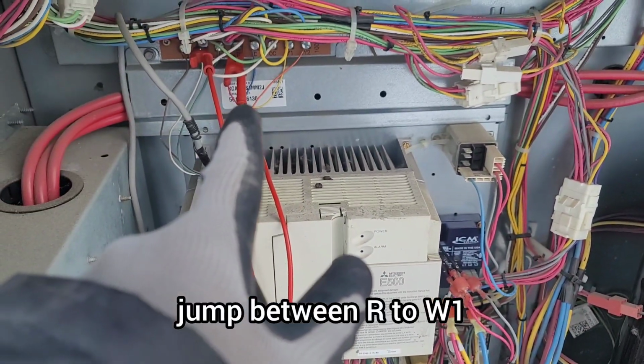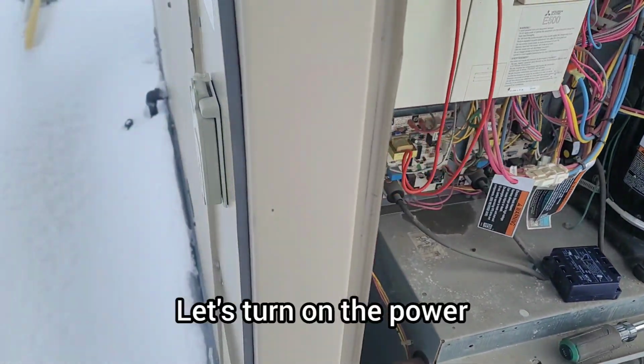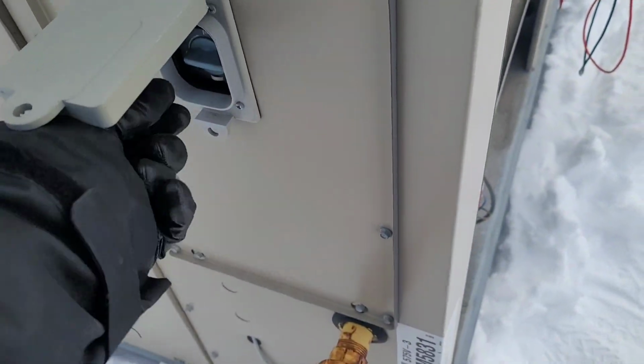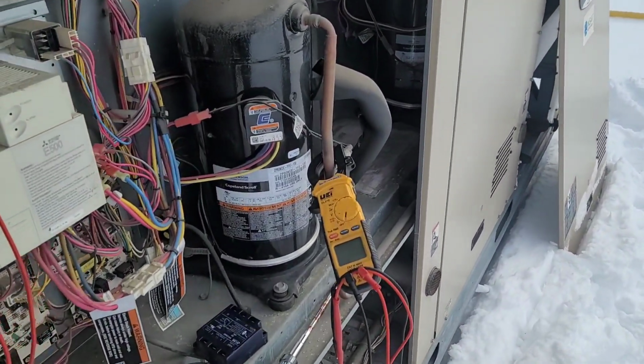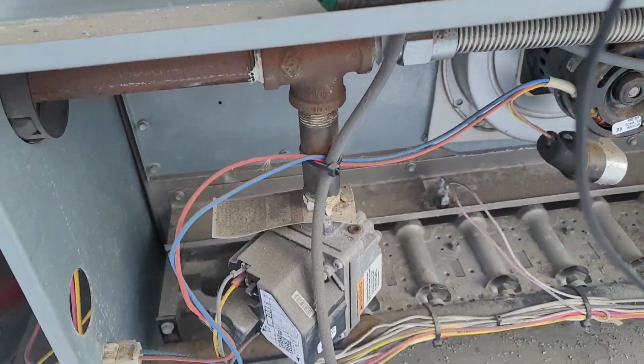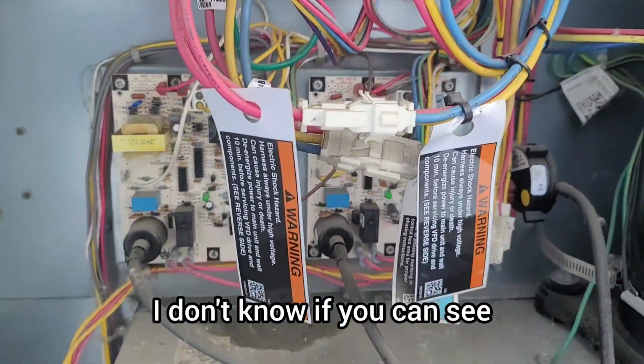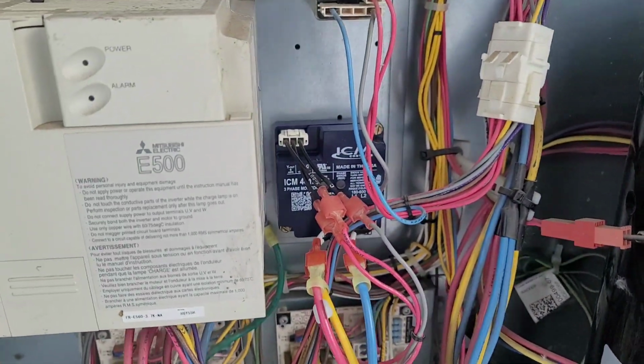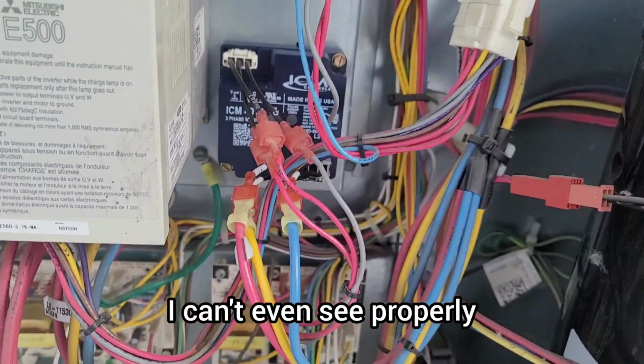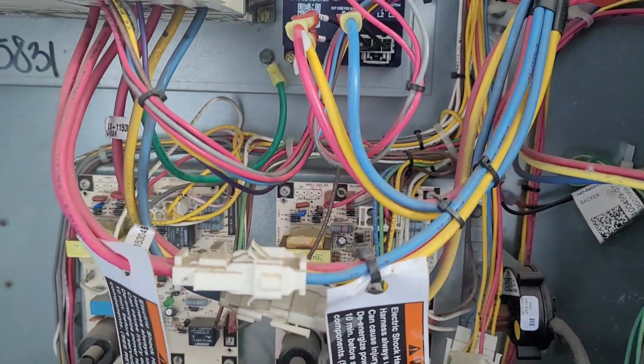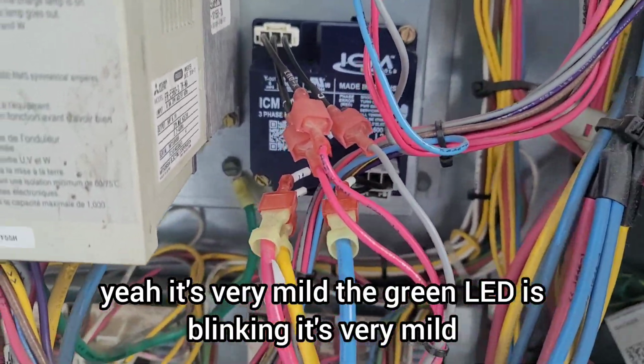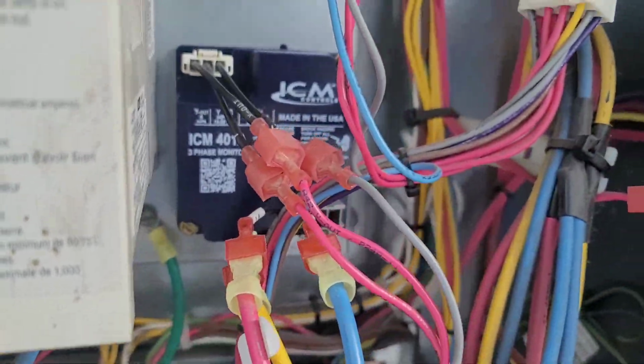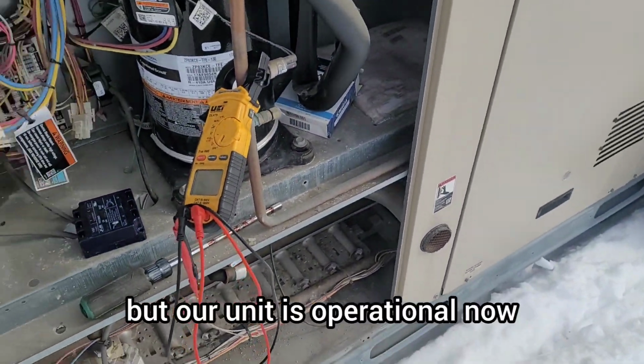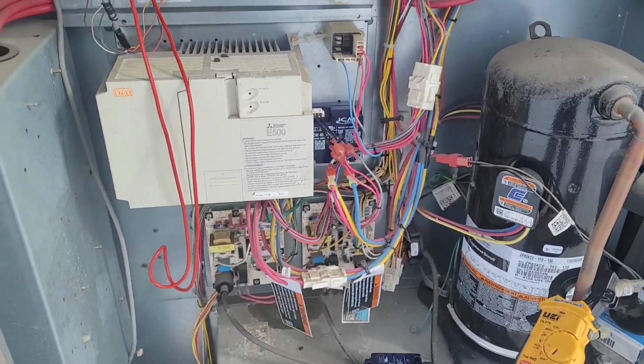So jump between R to W1. Let's turn on the power. Okay, so the inducer motor started. I don't know if you can see, I can't even see properly. Yeah, it's very mild. The green LED is blinking. It's very mild. But our unit is operational now. So that was the issue. So unit fired up.